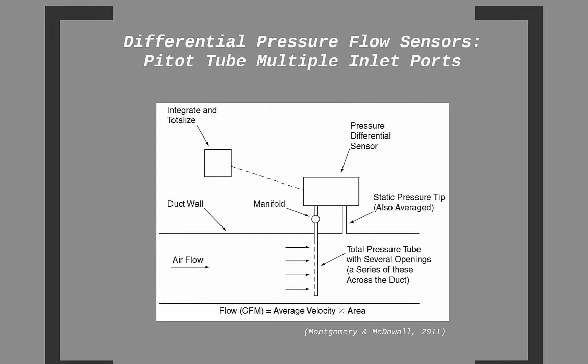The velocity profiles of flow streams are never consistent across the cross-sectional area. That means if the pitot tube was placed on the edge of a duct, it would measure a different velocity than if it was put in the center of the duct. Therefore, it is not uncommon to place sensors with multiple inlet ports to get a more representative value of the total pressure in the fluid stream.